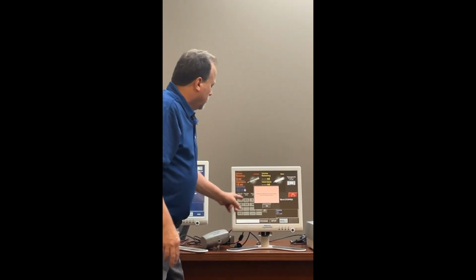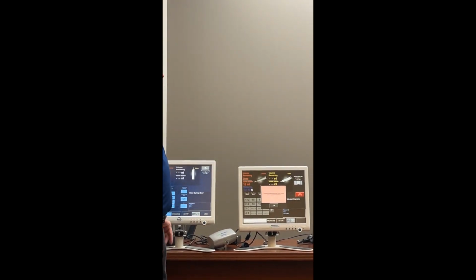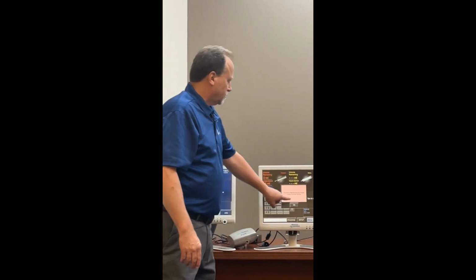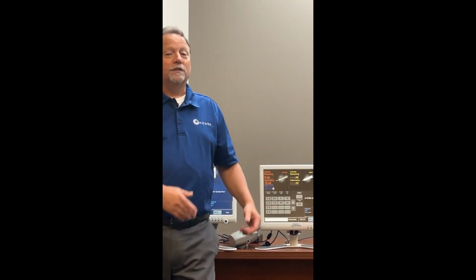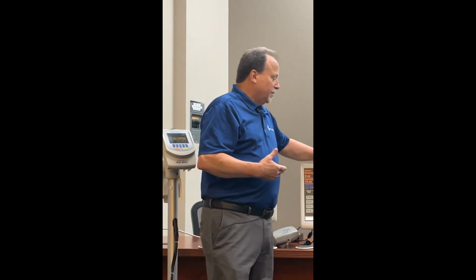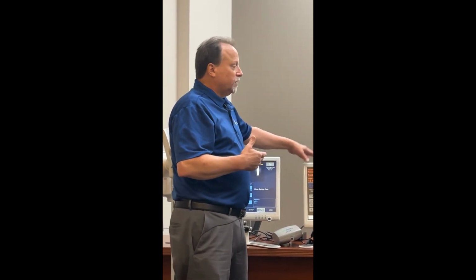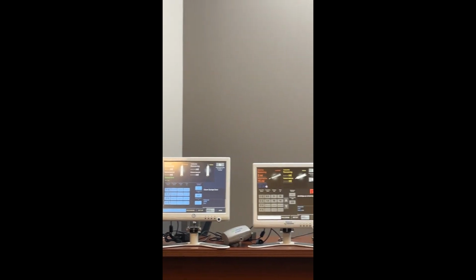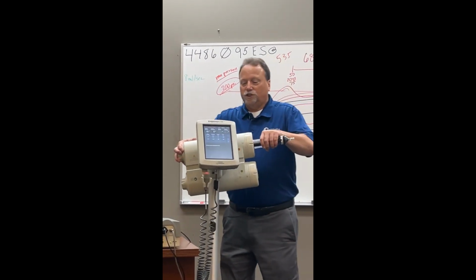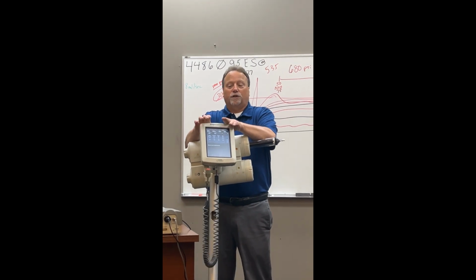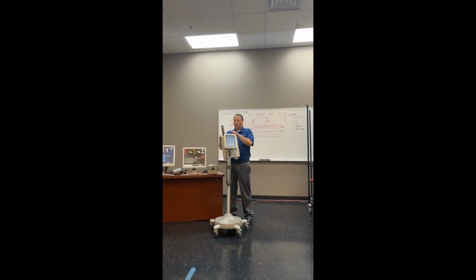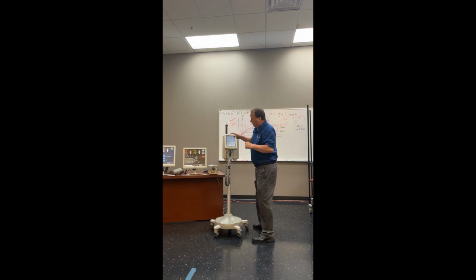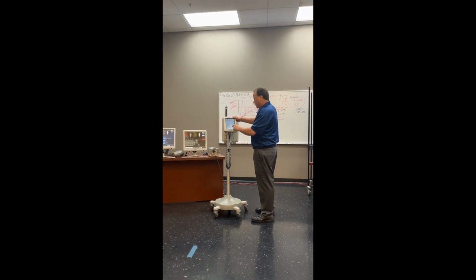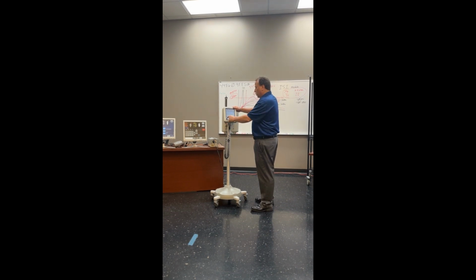So now we have this just popped up: Preventive maintenance due, please contact customer service. You can change that, and of course it's included in your training here at Althea. I can't get into that, but that can be done. So we did an injection. It is a unique injector in that it can be run individually from the control module in the scan room. So let's go ahead and replace the syringe. We're going to do it single.